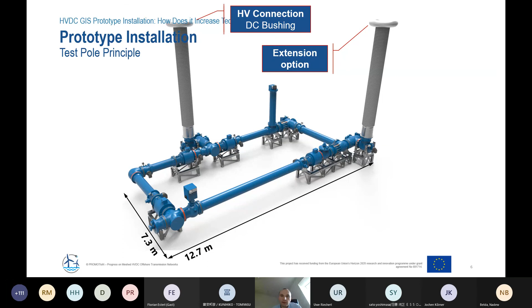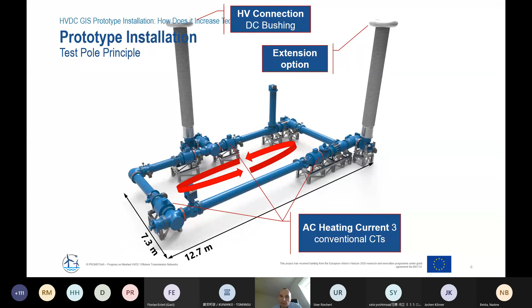Yeah, you've seen the picture of the test pole already from Nadu. It has the form of a ring, and it has 2 SF6-to-air bushings to connect to high voltage. The second bushing was used for the subsequent test, where we also tested the withstand of the disconnector in isolating distance. And to be able to heat up the test pole, we had conventional heating current transformers to drive a current of the rated current, 4000 amps, through the ring for long times, and to be able to also operate it at elevated temperatures.